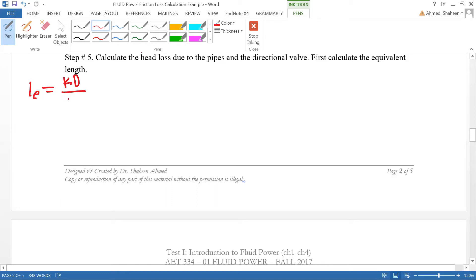The equivalent loss in a straight pipe in comparison to that fitting or valve. In this case we have a four-way directional valve with K value of 4, diameter of 3 inches, and friction value from the Moody diagram of 0.022.